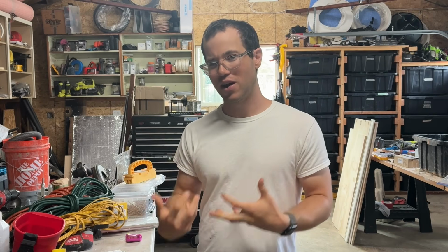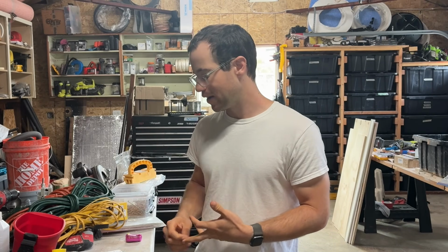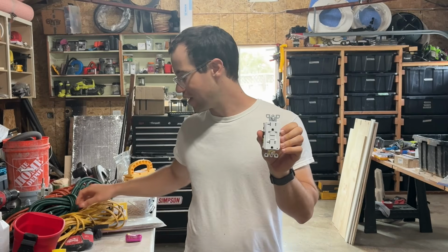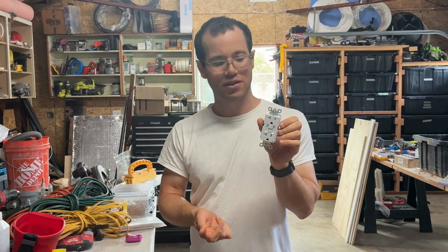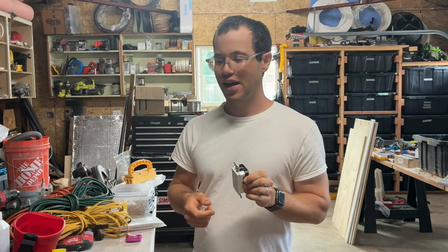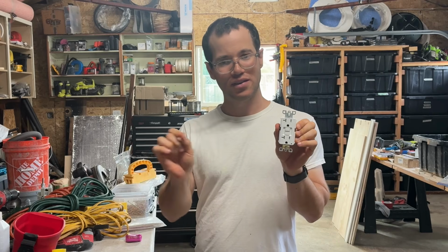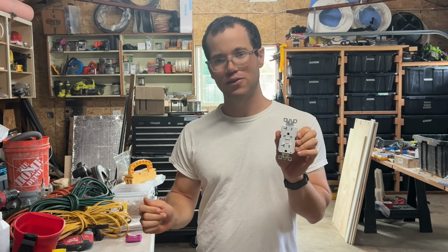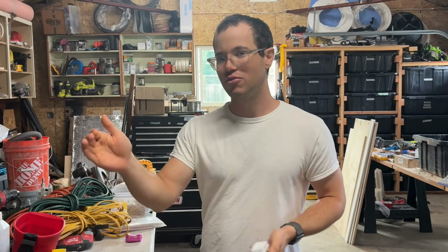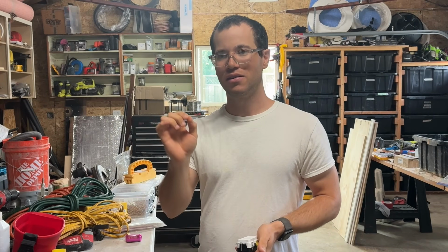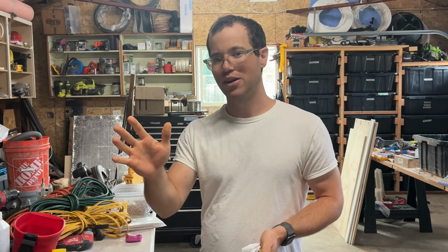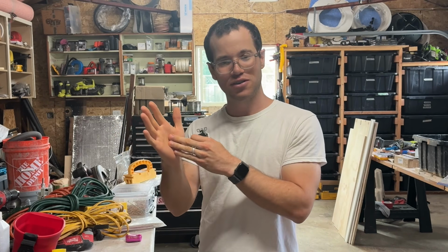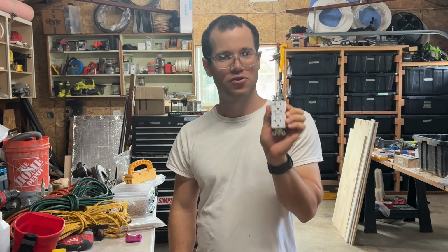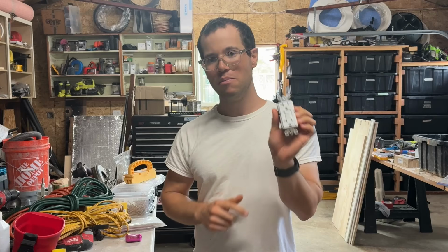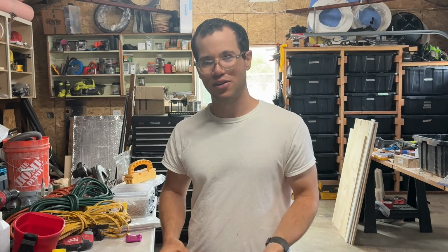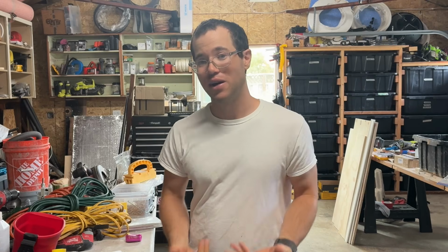So even though there isn't a ground wire, if we had plugged a toaster into this outlet and somewhere inside the hot wire was contacting the metal enclosure - say of a microwave - and you touched that microwave, within 40 milliseconds of those electrons flowing through you, the GFI will have tripped. It's a safety feature meant to save people's lives. This isn't just cutting corners - it's putting people's lives at risk, which is why it's a code violation.